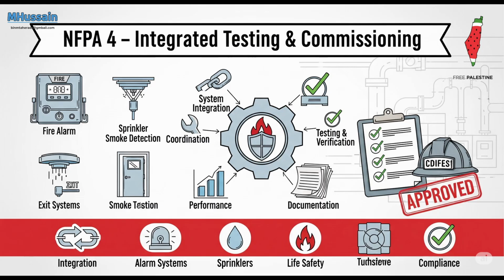Assessing the risks of the test. Why? Because the tests themselves cannot endanger anyone. Not the building occupants, not the personnel doing the test, not the building itself or its contents or its normal operations. You can't cause an emergency while testing for one. Makes perfect sense. Who's responsible for that risk assessment? The ITA, the Integrated Testing Agent, is responsible for making sure that assessment is done and documented.